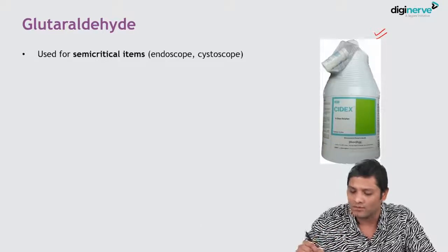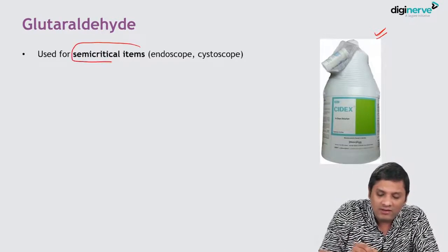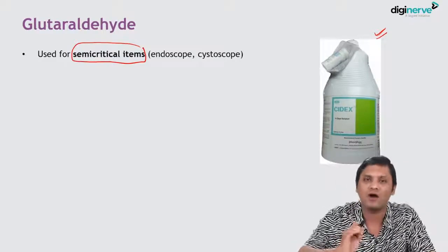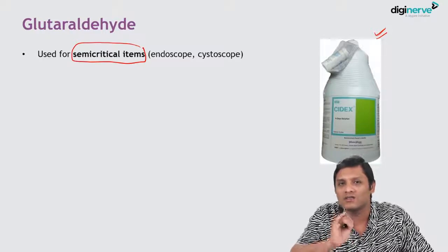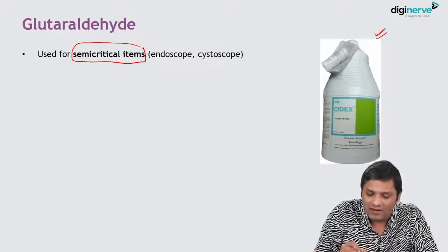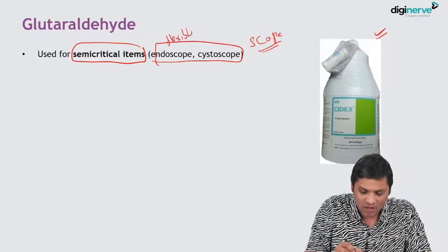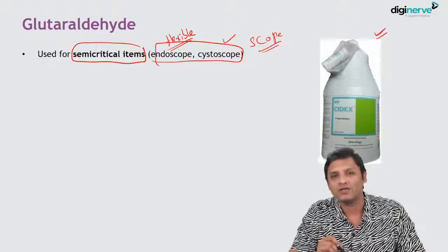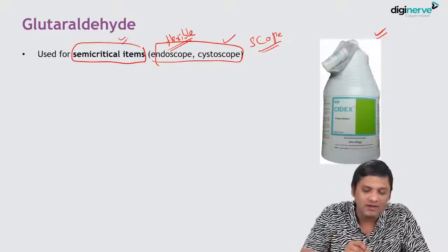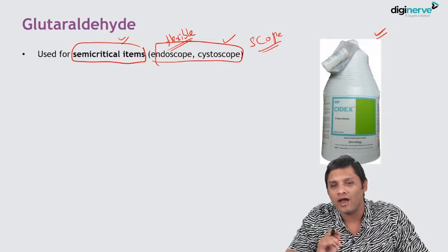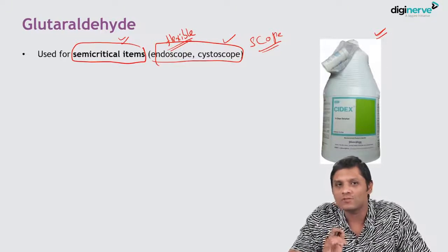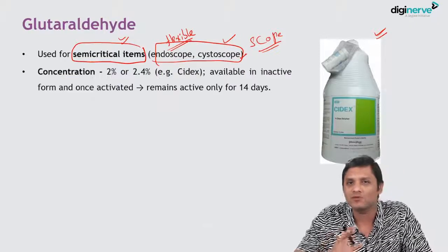Glutaraldehyde is commercially available as Cidex. It is used for the disinfection of semi-critical items. Glutaraldehyde is the most common disinfectant used for semi-critical items like scopes — all kinds of scopes including flexible endoscopes, cystoscopes, and laryngoscopes. These are items which enter sites where normal flora is expected to be present, and glutaraldehyde is the disinfectant of choice for those scopes.